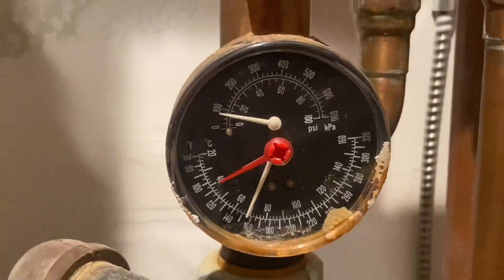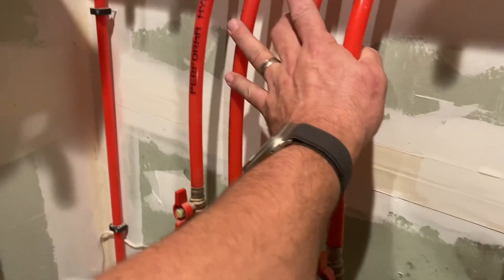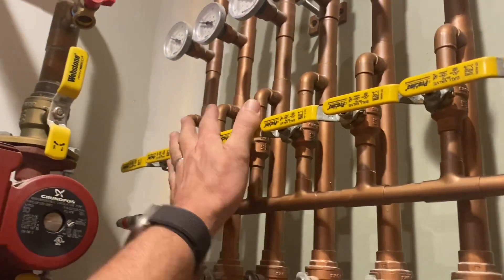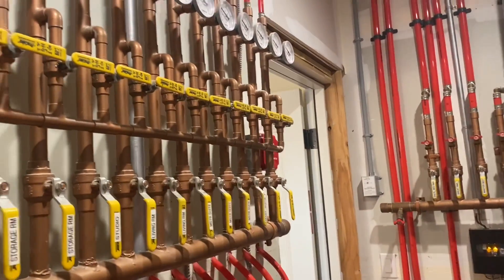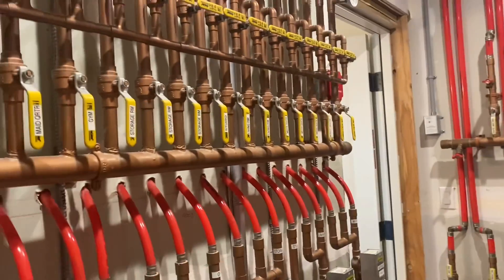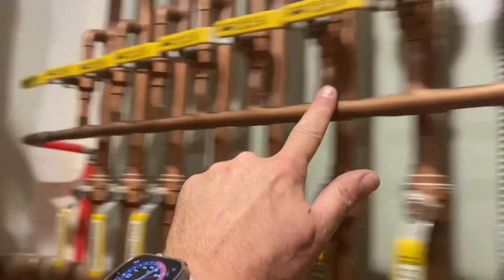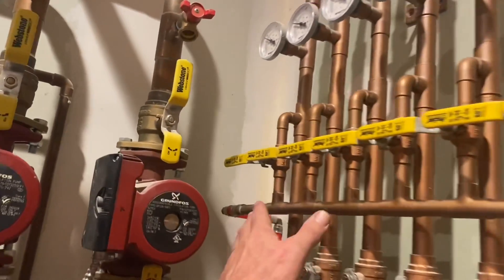This is our supply and this is the return. Holy sh*t — wow. You know what all these are for? Take a wild guess. Let's follow the pipe. All these are closed, and they're all coming off the return right here with T's. Wow — these are built-in drain stations, purge stations for every single one. This is really well done.